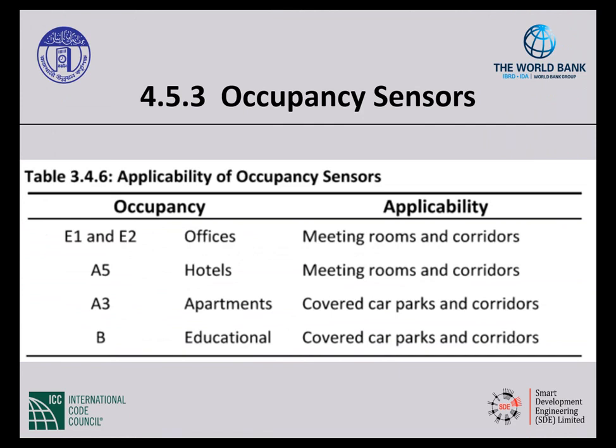It tells us in 4.5.3 that we need occupancy sensors, right? It says that in order to limit the use of electricity in the unoccupied areas of the building, occupancy sensors are linked to the lighting, except for emergency and security lighting. They shall be installed in the public areas of the buildings of these occupancies: the E's, A5, A3, and B's, office, hotels, apartments, and education. The public portions of the building, so it's applicable to meeting rooms and corridors, covered parks and corridors in those occupancies. So we need occupancy sensors.